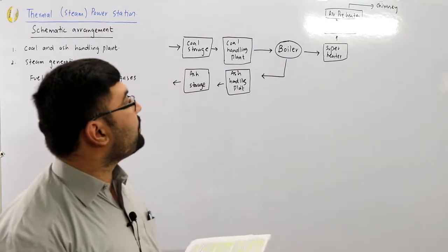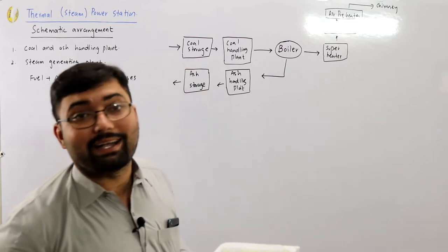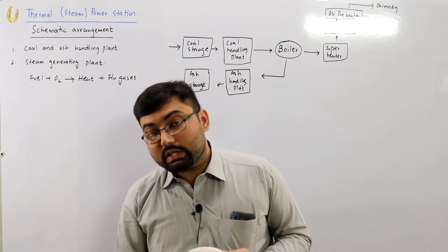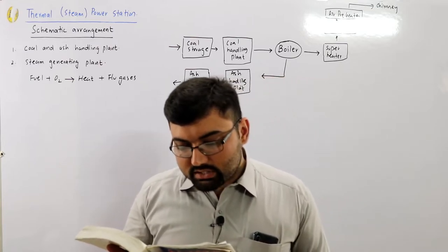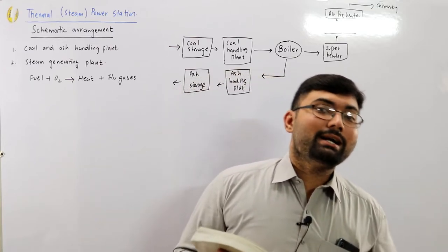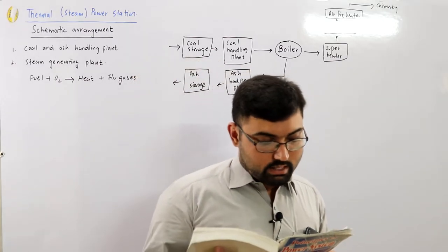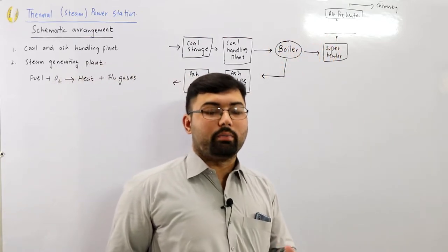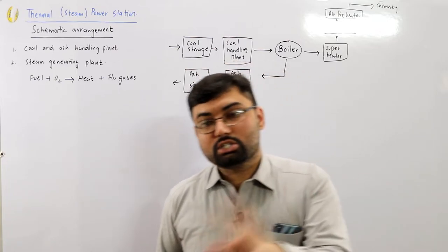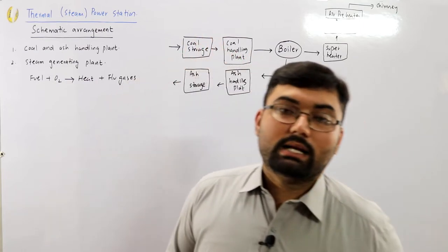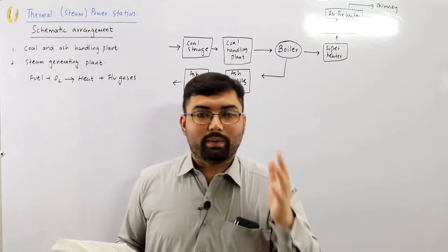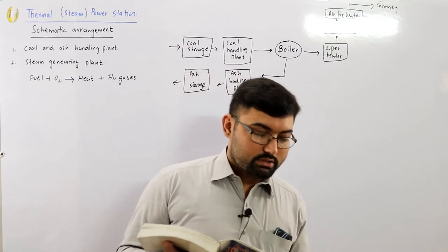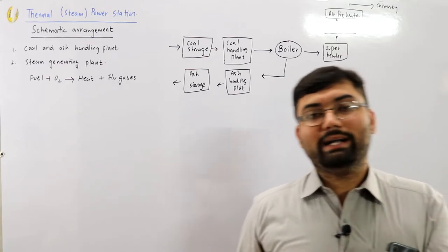The superheater: the steam produced in the boiler is wet, so it is passed to the superheater, which increases its temperature and dries it up — the steam temperature is raised beyond the boiling point of water using the heat from the flue gases on their way to the chimney. Superheating provides two principal benefits: increased overall efficiency, and dry steam is supplied to the turbine, preventing corrosion.